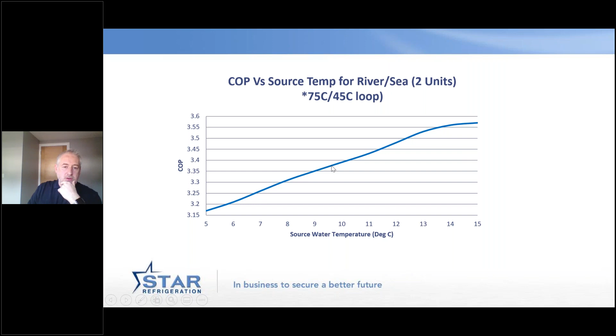I did a quick calculation before I came on here. The guys in Drammen, if they vary their COP by about 10%, so that's varying from 3 down to 2.7, that will cost them £1.2 million over the life of the plant. So a very simple adjustment in COP equals a massive cost difference in the overall plant performance. The heat pumps in Drammen, incidentally, were probably around about £5 million, something like that. And so 1.2 million, that's probably about 25%. So by varying the COP by 10%, we've equaled the value of 25% of the overall project cost.